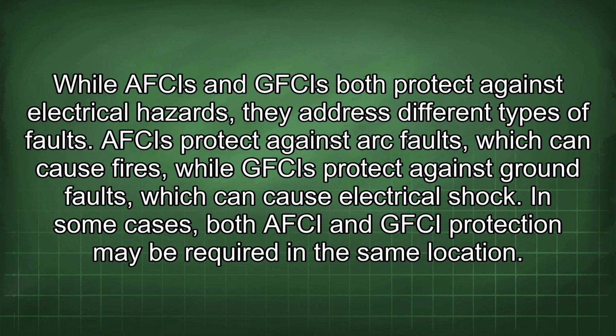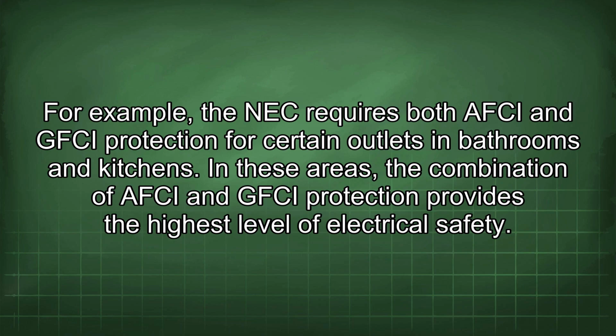While AFCIs and GFCIs both protect against electrical hazards, they address different types of faults. AFCIs protect against arc faults, which can cause fires, while GFCIs protect against ground faults, which can cause electrical shock. In some cases, both AFCI and GFCI protection may be required in the same location. For example, the NEC requires both AFCI and GFCI protection for certain outlets in bathrooms and kitchens. In these areas, the combination of AFCI and GFCI protection provides the highest level of electrical safety.